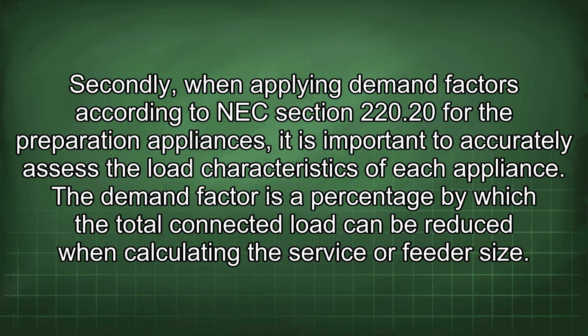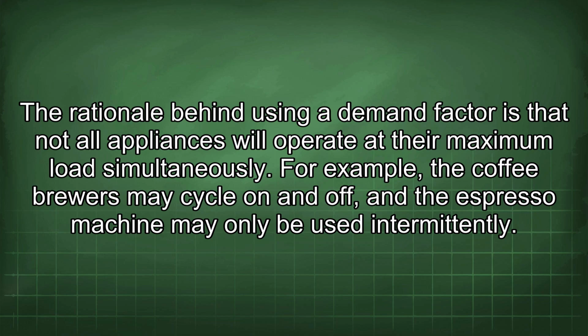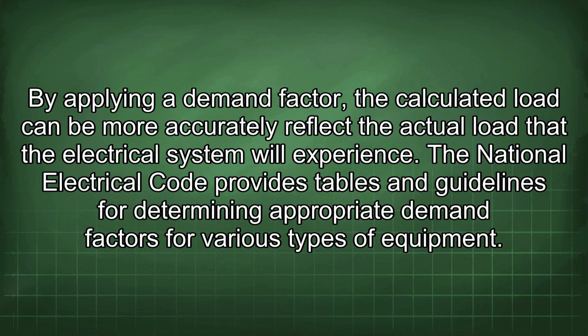Secondly, when applying demand factors according to NEC Section 220.20 for the preparation appliances, it is important to accurately assess the load characteristics of each appliance. The demand factor is a percentage by which the total connected load can be reduced when calculating the service or feeder size. The rationale behind using a demand factor is that not all appliances will operate at their maximum load simultaneously. For example, the coffee brewers may cycle on and off, and the espresso machine may only be used intermittently. By applying a demand factor, the calculated load can more accurately reflect the actual load that the electrical system will experience. The National Electrical Code provides tables and guidelines for determining appropriate demand factors for various types of equipment.